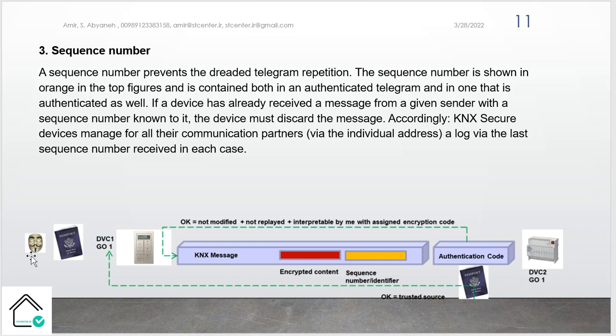Number 3 is sequence number. A sequence number prevents the dreaded telegram repetition. The sequence number is shown in orange in this figure. It is contained both in an authenticated telegram and in one that is encrypted as well. If a device has already received a message from a given sender with a sequence number known to it, the device must discard the message.